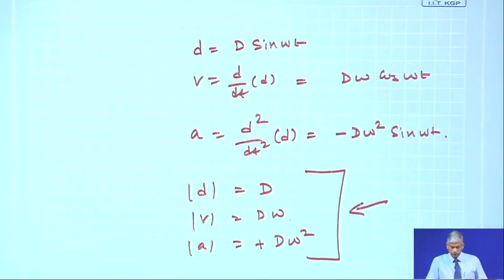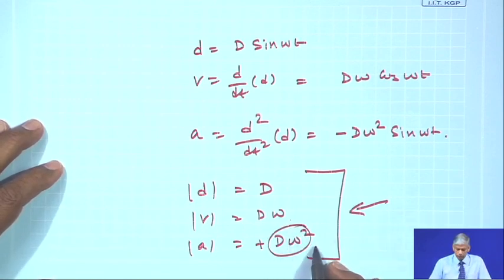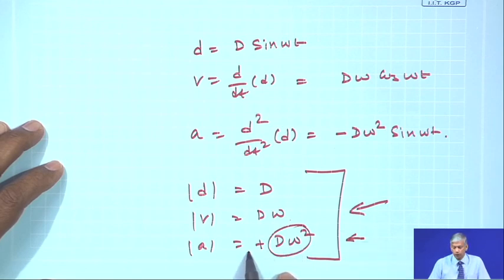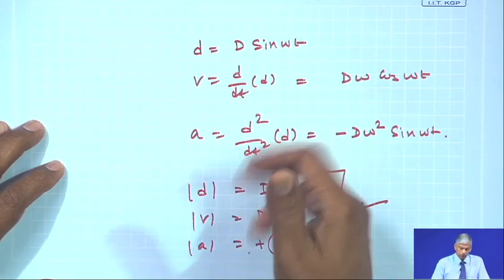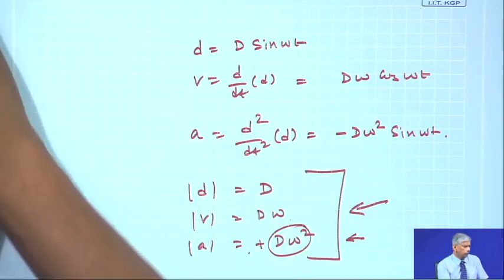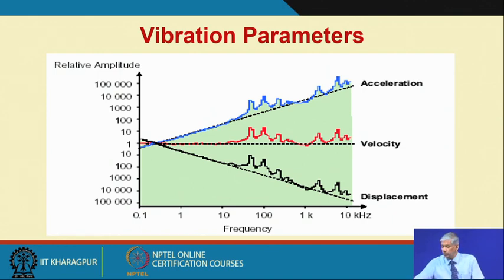A common question is: what is the best parameter to measure for CBM? At high frequencies, measure acceleration because ω² is large, giving good signal-to-noise ratios. At low frequencies, displacement is good enough. Some standards recommend measuring velocity since it is approximately linear in the log scale. Nowadays piezoelectric accelerometers are widely available; by knowing one parameter and the frequency you can compute the others.